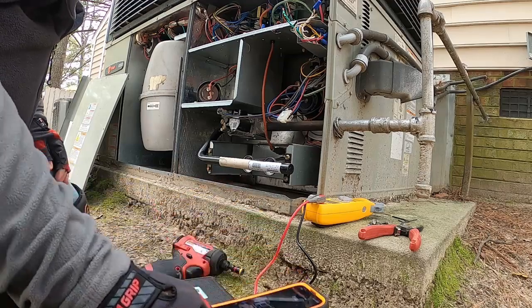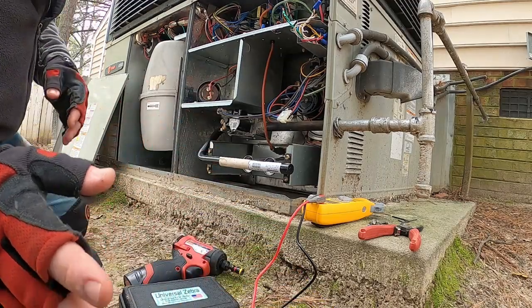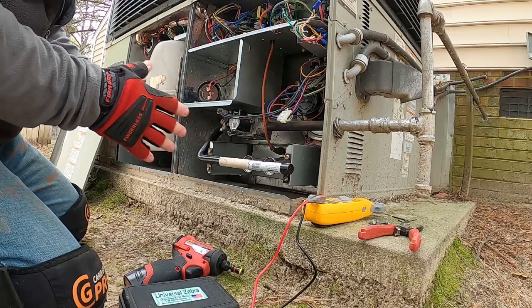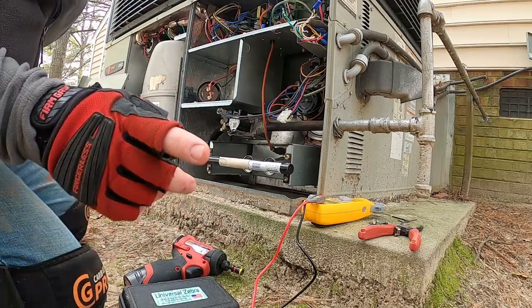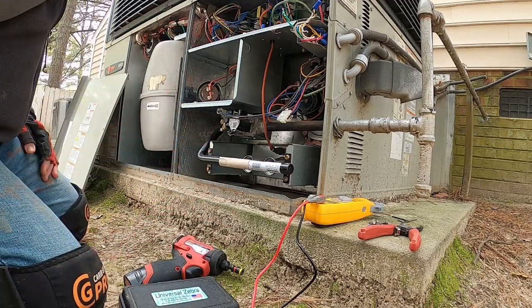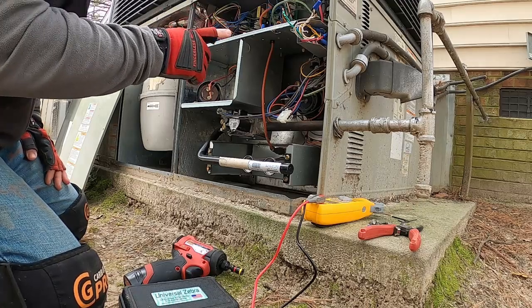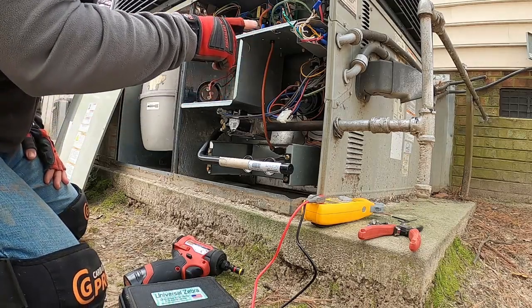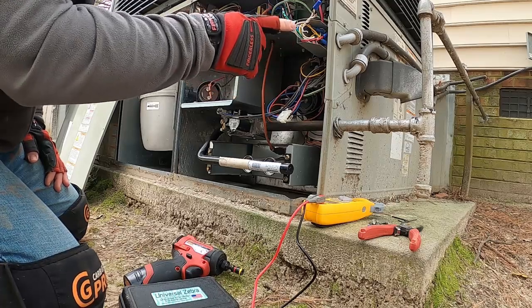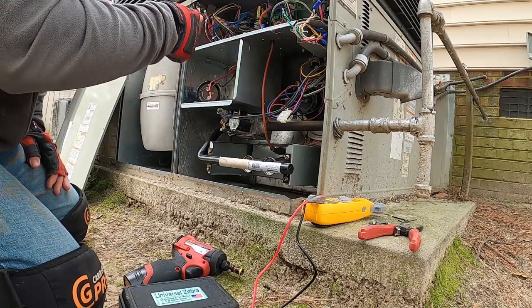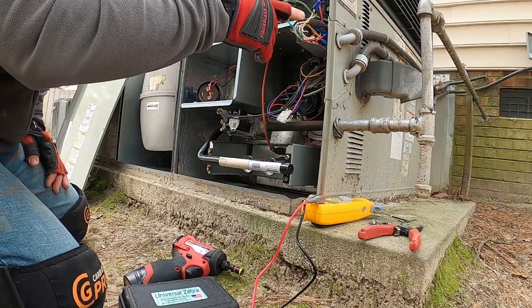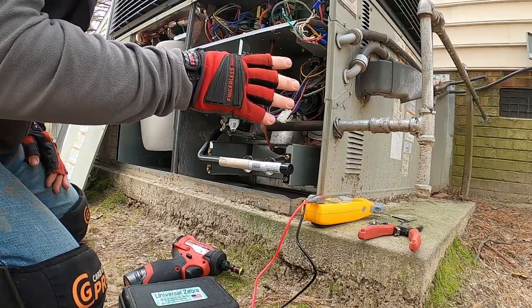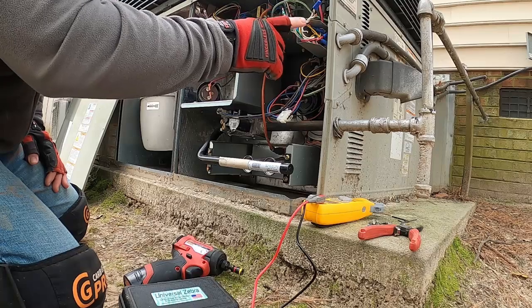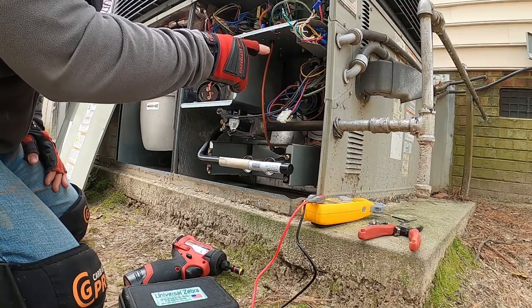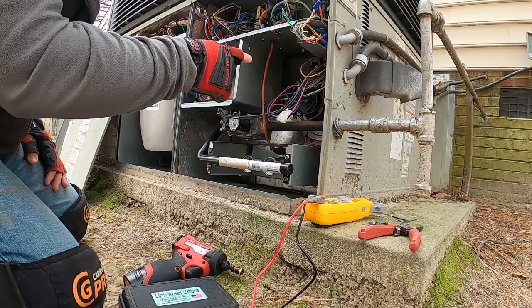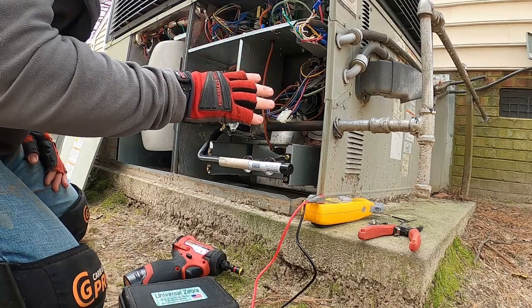So I recorded this part after I closed out the video, and now I'm editing it in because I thought about doing something. One of the faults these things will do is if that pressure switch is stuck closed, when it gets a call for W from the thermostat, it's going to go into that fault. Now that board's telling this thing to run constantly. I already know that's a problem. But that means when it gets a call, that switch is already closed. So when it does that test cycle, it's not going to fire off.